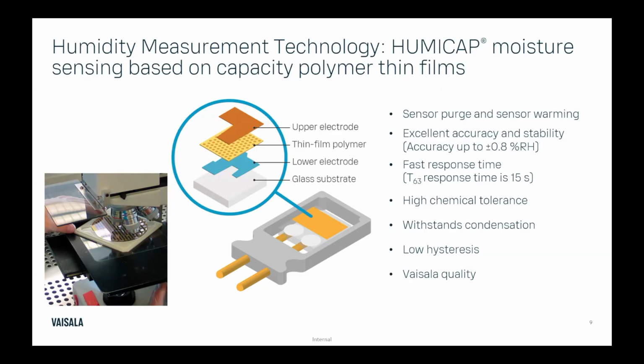The benefit of using this, as opposed to the early days hair hygrometers, is that they're much smaller. You'll see on the left is actually a wafer chip. So we produce our own humidity sensors. That chip has about 100 sensors on it, and then they are cut into pieces and integrated into our instruments specifically. So they're much smaller, which allows us to do a lot more with them, and also offers a very fast response time, with our T63 response time being about 15 seconds.